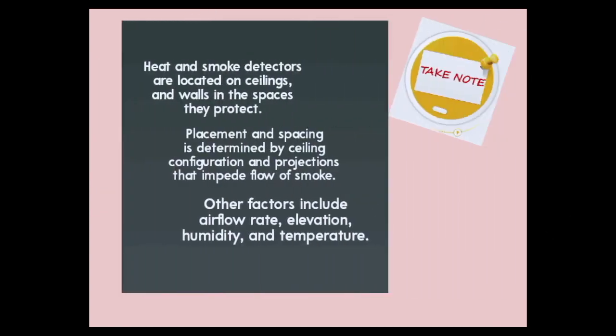Also take note, heat and smoke detectors are located on ceilings and walls in the spaces they protect. Placement and spacing is determined by ceiling configuration and projections that impede flow of smoke. Other factors include airflow rate, elevation, humidity, and temperature.